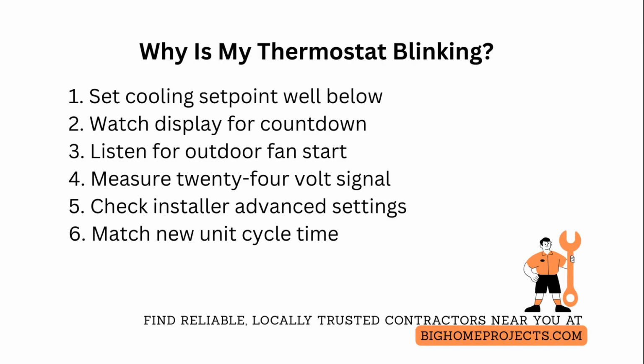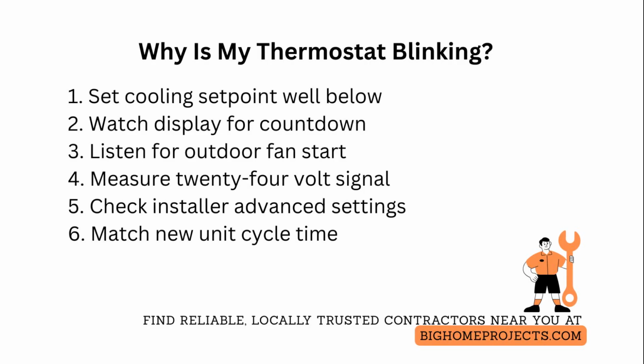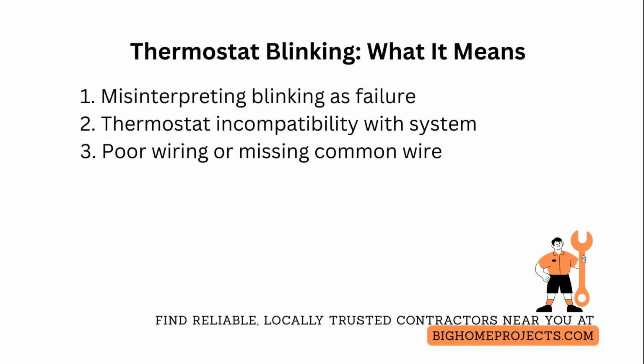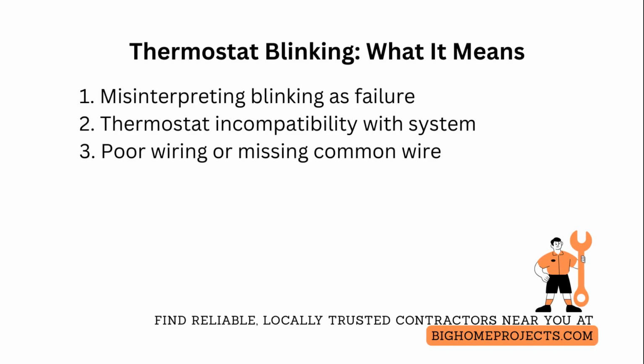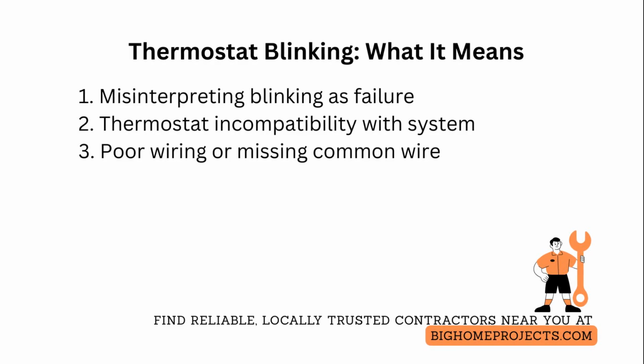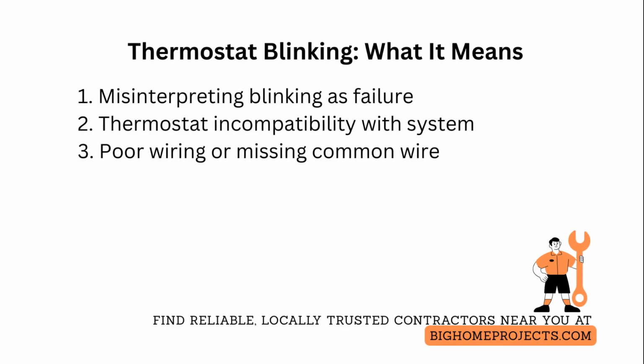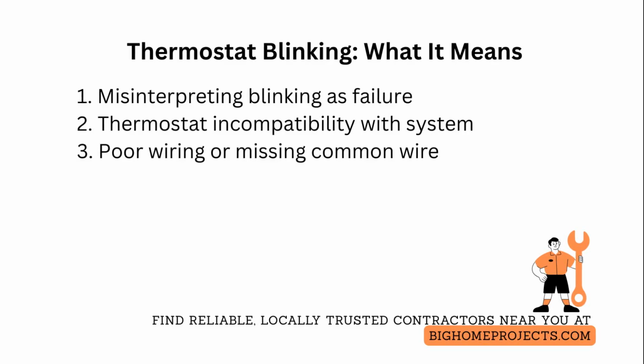Always disconnect power at the service panel before doing wiring changes, and label wires during thermostat removal to preserve correct staging and fan control. One of the most common mistakes is misinterpreting thermostat blinking as a control failure, thermostat not calling for cooling. Fix this by checking the installer settings, listening for outdoor unit fan action, and confirming the 5-minute protection timer is active in documentation or service menus.